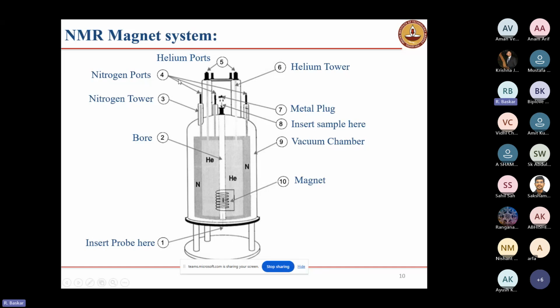These are the nitrogen towers. This is the bore. As I already told, two kinds of bores are there, the standard or narrow bore and the wide bore. It depends on the probe and on what experiments we need, so depending on our requirement we can buy. Generally, with the wide bore the liquid helium evaporation will be more. We have to fill at least once in three months.